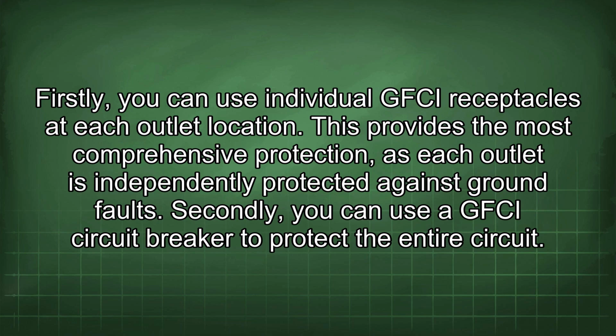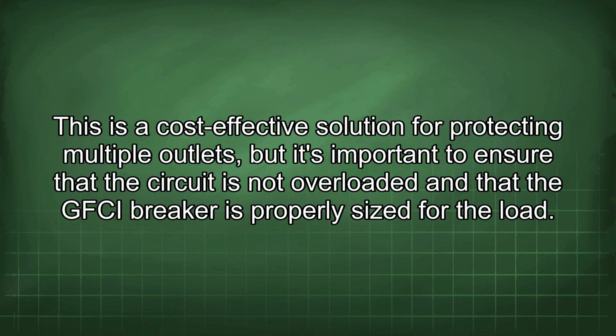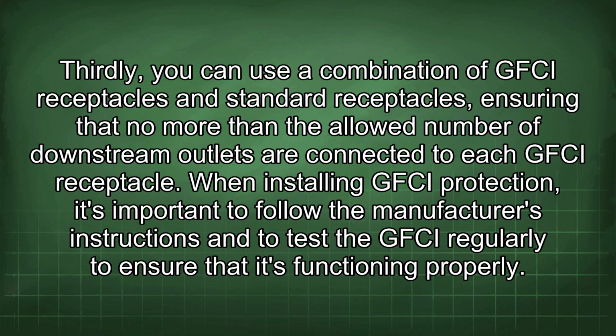Firstly, you can use individual GFCI receptacles at each outlet location. This provides the most comprehensive protection, as each outlet is independently protected against ground faults. Secondly, you can use a GFCI circuit breaker to protect the entire circuit. This is a cost-effective solution for protecting multiple outlets, but it's important to ensure that the circuit is not overloaded and that the GFCI breaker is properly sized for the load. Thirdly, you can use a combination of GFCI receptacles and standard receptacles, ensuring that no more than the allowed number of downstream outlets are connected to each GFCI receptacle.